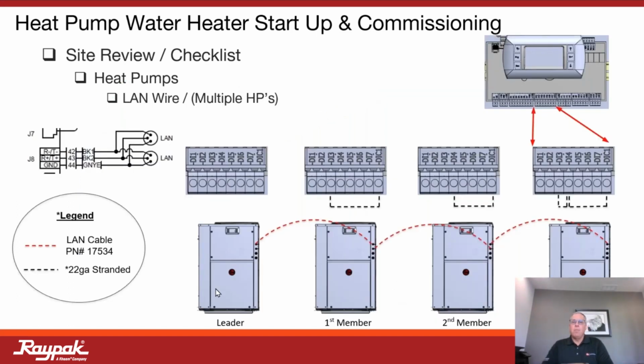The wiring, again, I would hazard a guess to say most of our projects for domestic water production as well as space heating are going to be multiple units. So again, we used the words earlier of local area network wiring, or what in the boiler world or water heater world we would consider to be cascade. As a common thread, it's very common to get to a job site and the low voltage wiring is not done. I mean, it happens all the time. So again, we like that sign-off checklist.